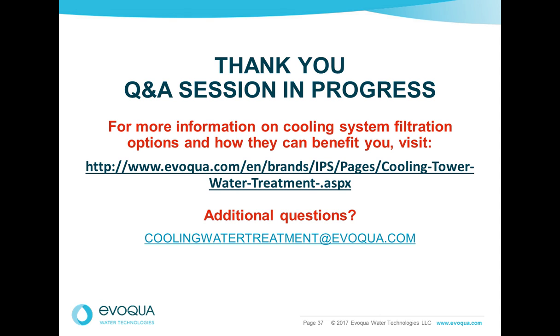Speaking of filter proportions, we had a question come in. A general sidestream filtration proportion was given as 3 to 5%. The audience member wants to know what the basis is for this rule of thumb, and how one can determine the design flow rate based on data gathered from the cooling water? So the 3 to 5%, I guess, comes from the filter manufacturers over time. Data collected, it's kind of a balance, as I said. You might say that it's experience.